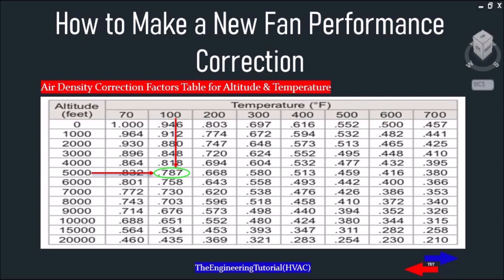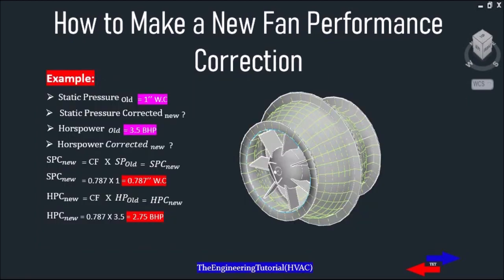The table allows us to select a correction factor based on altitude in feet and temperature. For an altitude of 5,000 feet above sea level and a temperature of 100 degrees Fahrenheit, the table reads a correction factor of 0.787. Static pressure old is 1 inch of water column, and horsepower old is 3.5; we need to find the corrected new values for both.